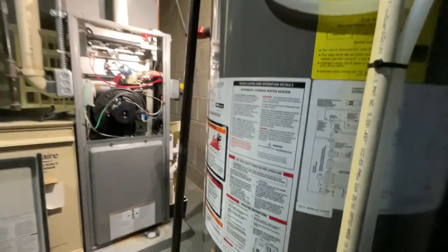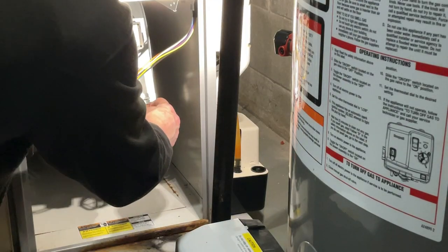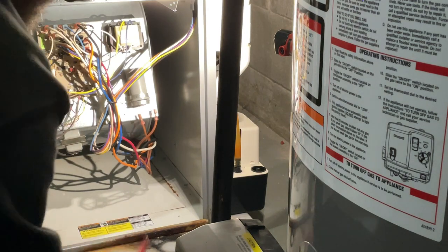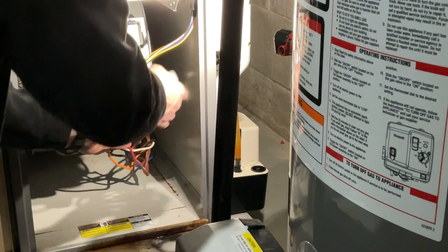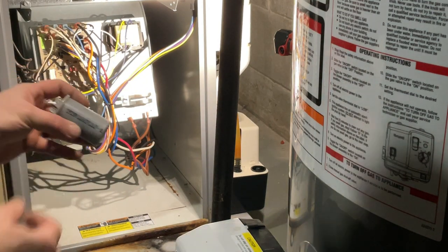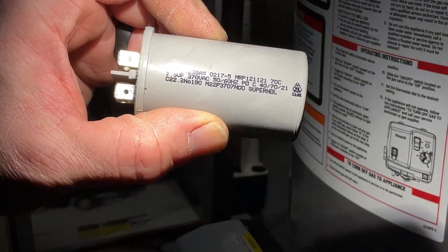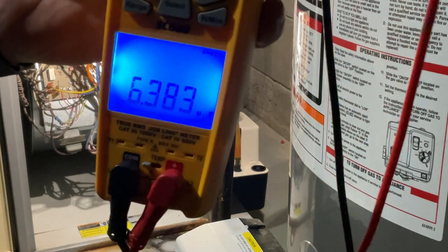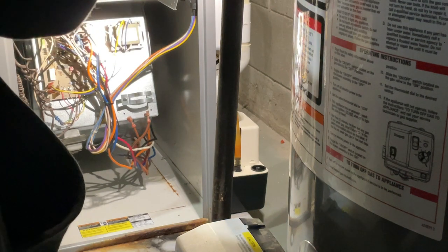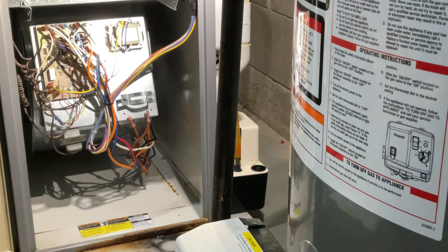Let's check the amp draw on the blower. First, let me check this capacitor. Let me just pop that out of there. This one is a 7.5. Let's see what it reads — 6.38. So this is weak. Let me go grab a replacement capacitor.